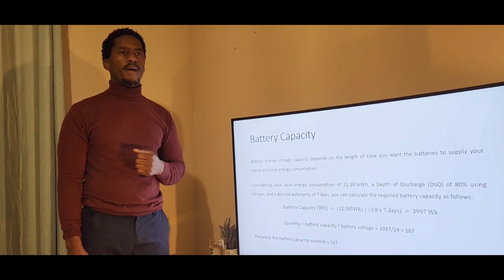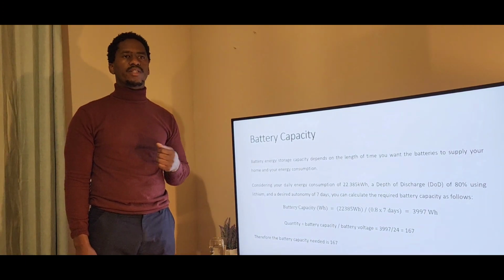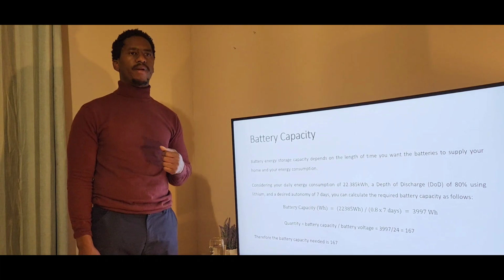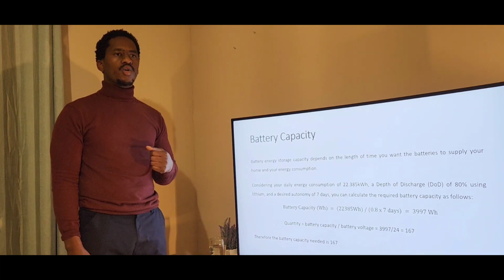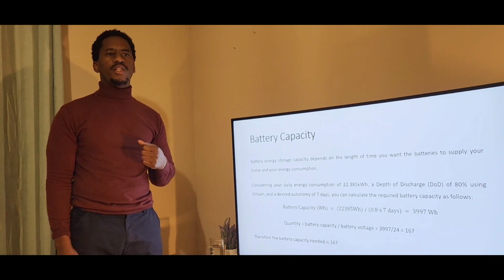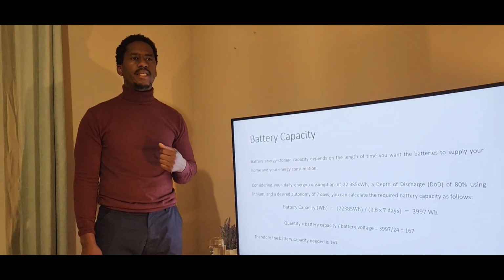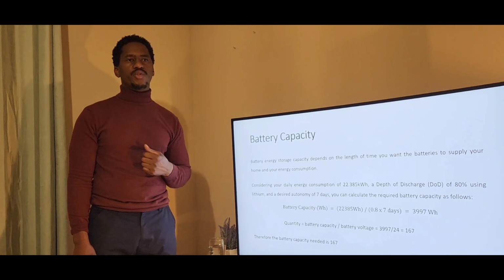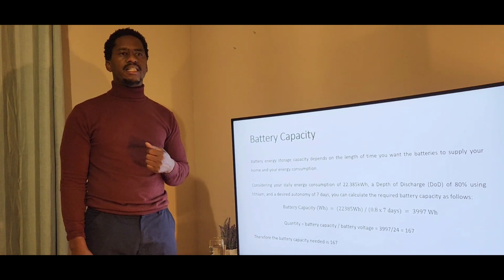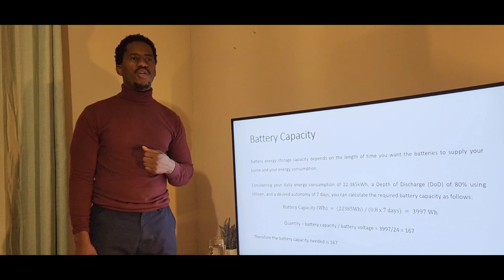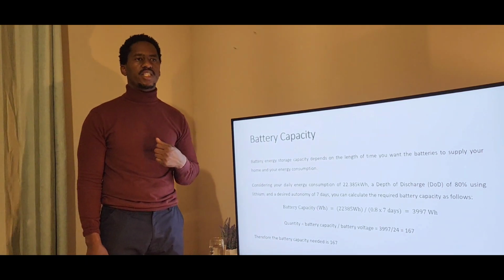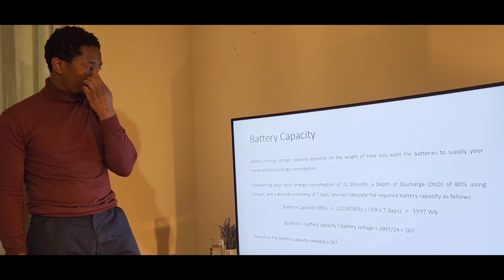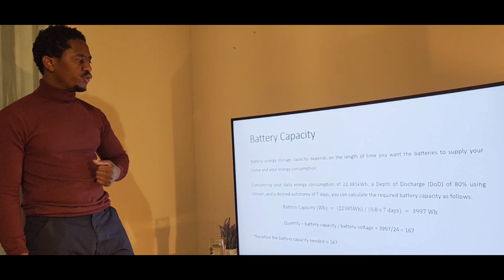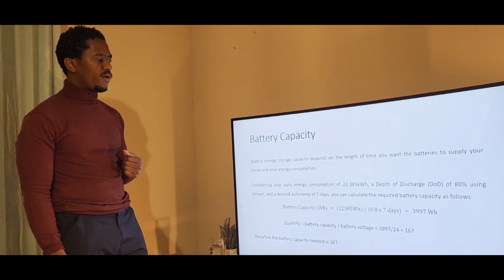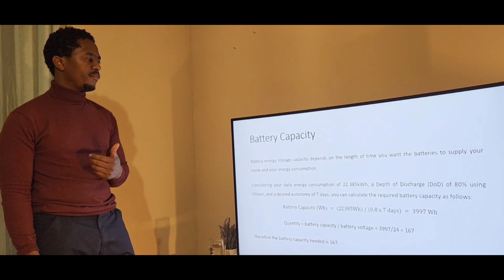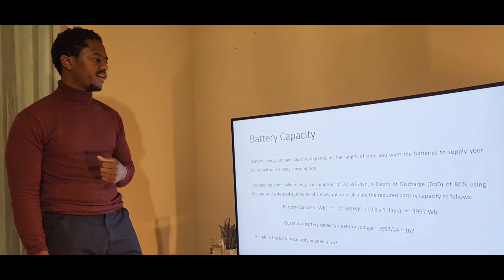Battery capacity. Battery energy storage capacity depends on the length of time you want the battery to supply your home and your energy consumption. Considering your daily energy consumption of 22.385 kilowatt-hours, a depth of discharge of 80% using lithium, and a desired autonomy of 7 days, you can calculate the required battery capacity as follows. Battery capacity in watt hours is 22,385 watt hours divided by 0.8 times 7 days.